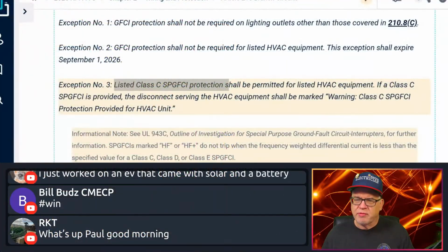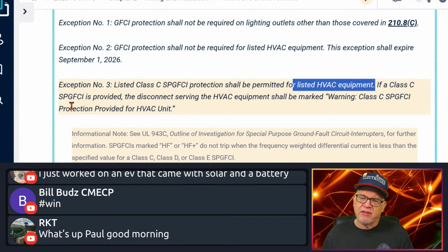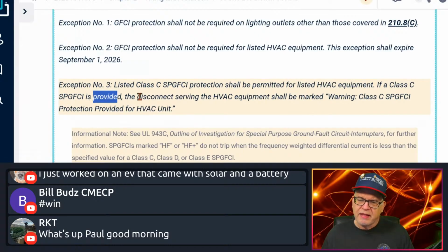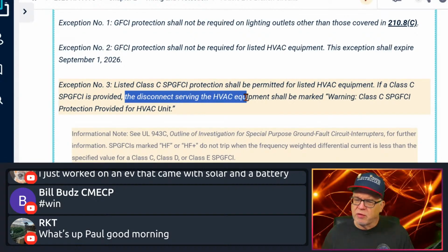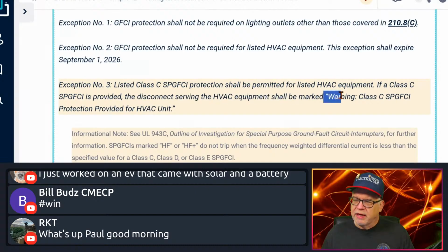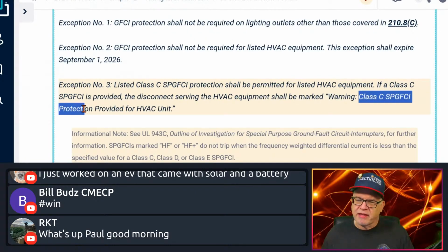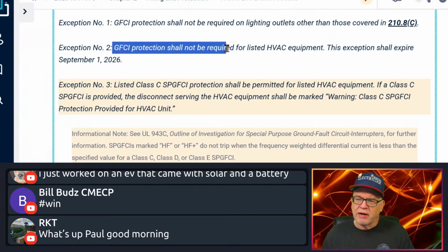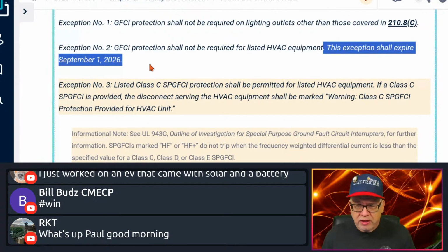So let's read the exception again. The code says exception number 3: listed Class C SP GFCI protection shall be permitted for listed HVAC equipment if a Class C SP GFCI is provided. The disconnect serving the HVAC equipment shall be marked: warning, Class C SPGFCI protection provided for the HVAC unit. Now you still have exception number 2 here that said GFCI protection shall not be required for listed HVAC equipment. This exception shall expire September 1st, 2026.